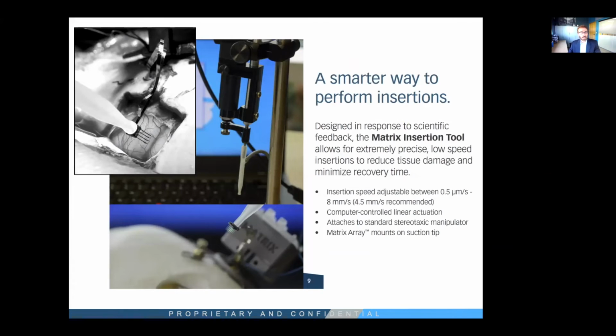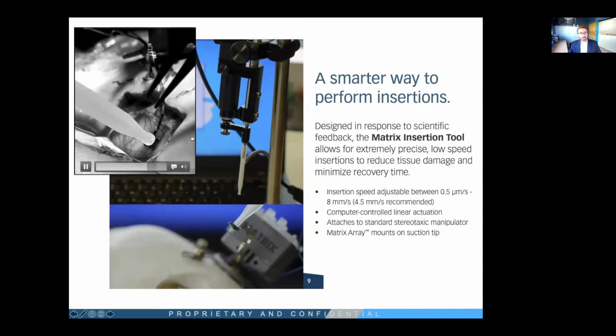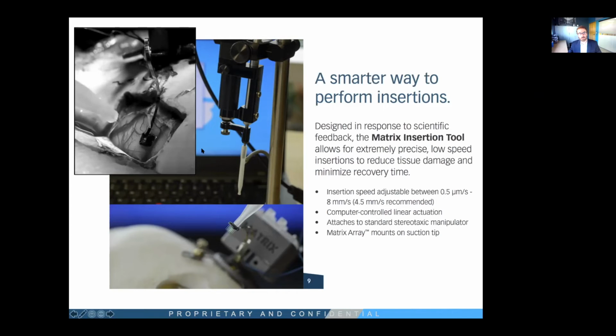And I mentioned earlier, we provide accessories. So we feel strongly about the importance and the value of a precisely controlled insertion. So this is a computer controlled inserter that can insert in steps of 0.5 microns per step, and up to speeds up to 8 millimeters per second. So this is a matrix array being implanted. This is a vacuum interface. So once the device is inserted, the vacuum is turned off, and then the insertion tip can be removed. In this case, you see the researcher was a little nervous the array might stick, so he had his tool there just in case. But upon removal, there was no sticking, and you can see the array is left afloat with the pulsations of the brain.